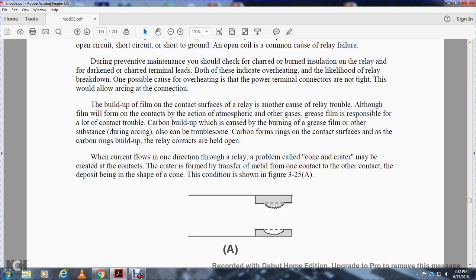arcing at the connection. A film building up on the contacting surface of the relay is another cause of relay trouble, although it will form on contacts acting in the atmosphere and other gases. Grease and film are responsible for a lot of contact trouble. Contacts that build up and are covered with burnable grease film or other substances during arcing can be troublesome. Carbon forms rings on contact surfaces, and as the carbon ring builds up, the relay contacts are held open.